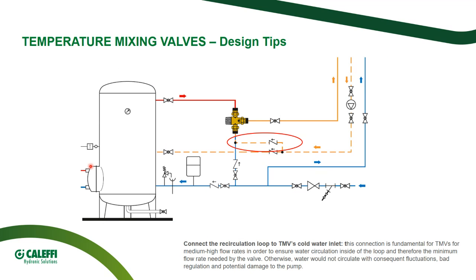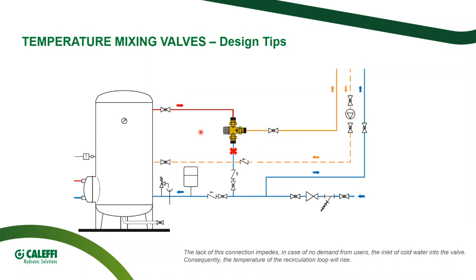is related to a very important connection that is often forgotten, the connection of the recirculated loop to the cold water inlet of the centralized mixing valve. This connection is crucial in order to grant the valve the minimum water circulation we discussed 1 minute ago. So let's suppose we forgot it. So let's take it out. And let's suppose there is no hot water demand from the users downwards.